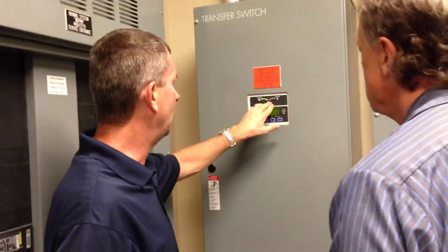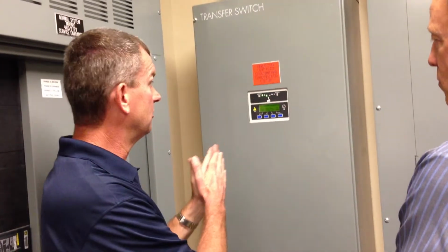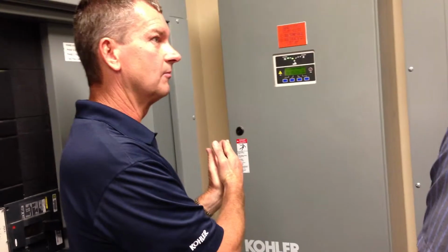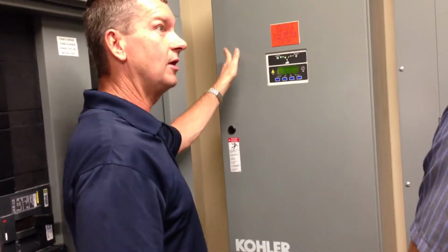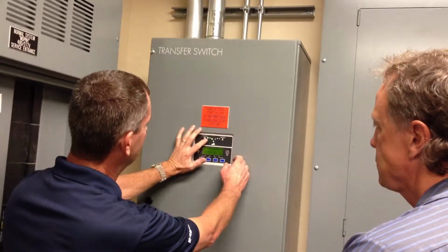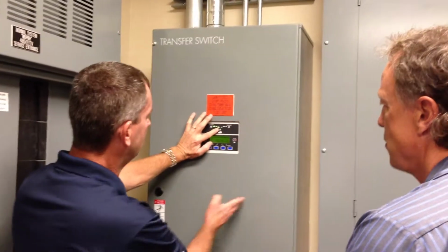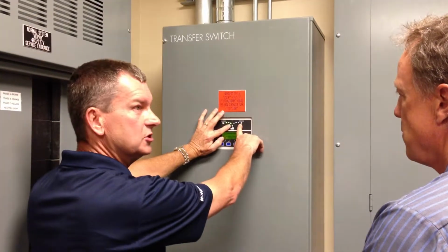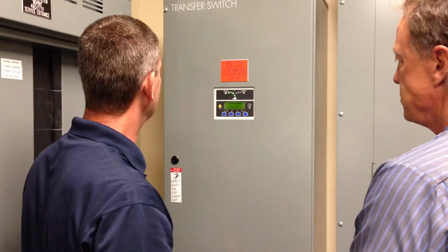What you will never have is this light and the one across from it on at the same time, because it's either gonna be in an emergency position or it's gonna be in a generator position. So, don't sweat it. When we were running the generator out there earlier, somebody standing here would have seen a green light that utility's present, a green light that the transfer switch is on utility, but a red light that the generator was running. So, that's all we have there.